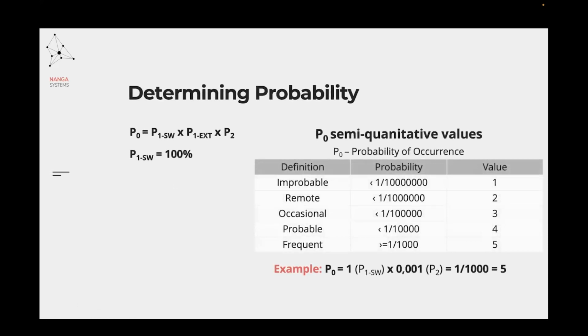In order for us to determine the classification or the class for the software safety classification, we have to evaluate the hazardous situations that might occur, and we have to determine the probability and the associated severity. In case of software development, we will talk about this a little bit more in detail later in this presentation. We have to separate P0, probability of occurrence, into P1 and P2 to effectively determine the appropriate probability. The reason behind this is that P1, because we are talking about software, which is one part of P0, is usually considered to be 100%, because if a failure might happen in case of software, it is most likely to happen.